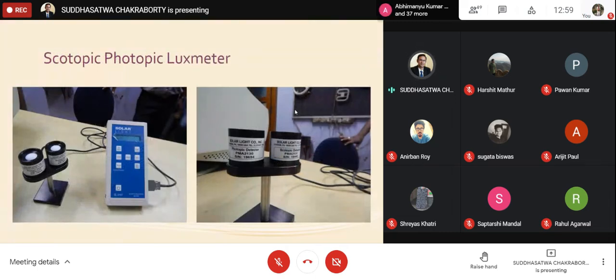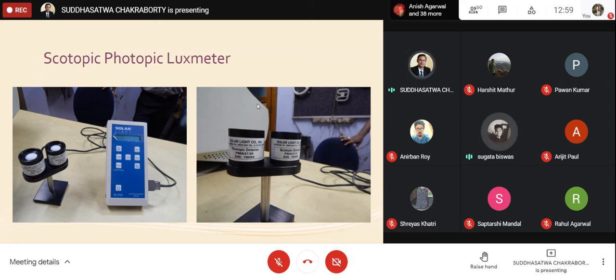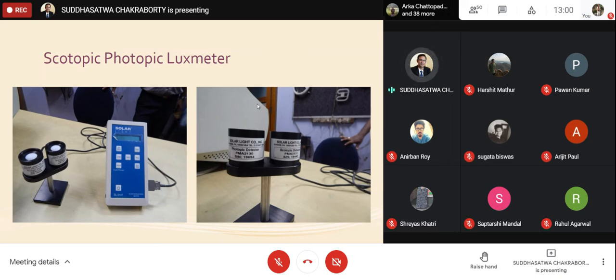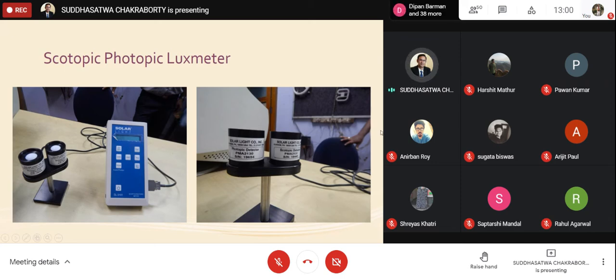We have lux meters with two scales: photopic and scotopic. The photopic lux meter uses a silicon photodiode with a V(λ) filter. The scotopic lux meter replaces that with a V'(λ) filter. These two filters correspond to the different human eye sensitivity curves — one for photopic and one for scotopic vision — giving us photopic and scotopic lux measurements respectively.